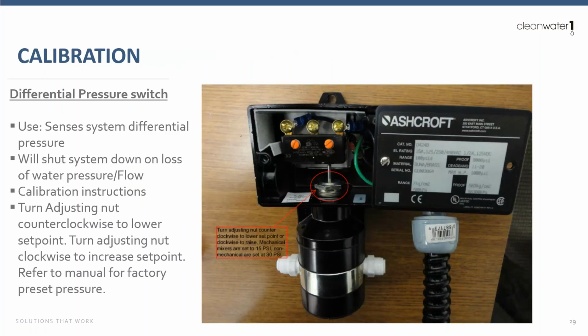There's a couple different items that are common between all of these skids, and one of them, depending on the different control options of the system, is a differential pressure switch. So this is essentially used to sense differential pressure of the system, and it's used to shut down the system on loss of water pressure or flow. It's important to understand, though, how to calibrate these, right? They come out with a factory preset of around 15 psi. These are adjustable. So in order to adjust the pressure settings, you can turn that nut clockwise or counterclockwise to increase or decrease the pressure.